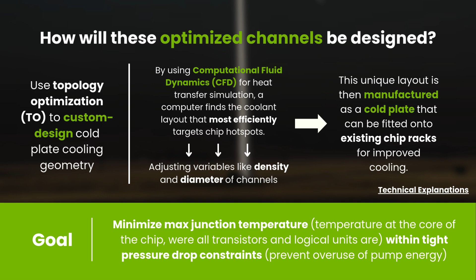We enhance chip cooling by reducing maximum junction temperature within pressure drop limits to lower pump energy consumption. Using real power maps, we conduct CFD simulations to locate hotspots and apply topological optimization for efficient cold plate designs. These manufacturable layouts with adjustable channel density and diameter can be retrofitted to existing systems, improving cooling performance and energy savings.